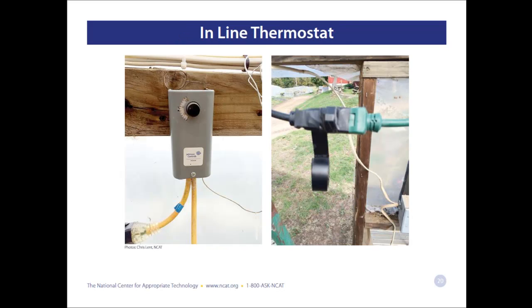We used a simple external temperature control thermostat that we put in line so that when it got below 35 degrees in the high tunnel, it would shut the unit down. That was to avoid the condensate freezing problem. And we taped all of our plug connections, mainly to keep moisture out of them, but also to make sure that none of them were pulled apart at any time during the winter. That would shut all the equipment down if one of these plugs came unplugged. So we made sure we taped all of those.